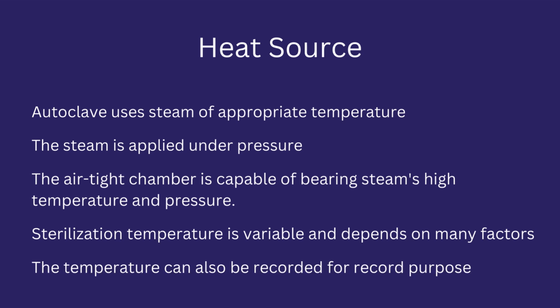The temperature is recorded for record purposes so that the same can be presented to the regulatory authorities during their inspection. In this application, the temperature is recorded versus time, such as per 20 seconds, 30 seconds, or other required interval.